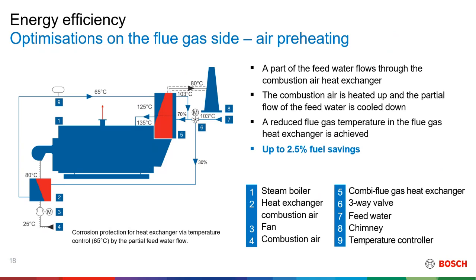We had this discussion previously where someone will ask, why am I heating the air that I'm going to burn? So just to explain the setup, here you will have feed water coming in from a pump or a feed water tank flowing from number 7, you can see. Then you'll have a 3-way modulating valve. Then you will have an economizer 6, and then you will have an air preheater, which will be the main components.